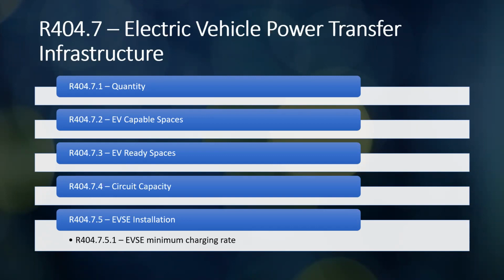space per dwelling unit. That does say R2 occupancies or allocated parking for R2 occupancies in mixed-use buildings shall be provided with EV capable space, EV ready space, or EV-SE space for 40% of the dwelling units or automobile parking spaces, whichever is less. And then you've got the capable spaces, and it talks about that. The requirements for that must meet. It's just basically saying a continuous raceway or cable assembly needs to be installed with an enclosure located within 3 feet of the space. An installed raceway or cable also has the size and rated capability for minimum circuit capability.